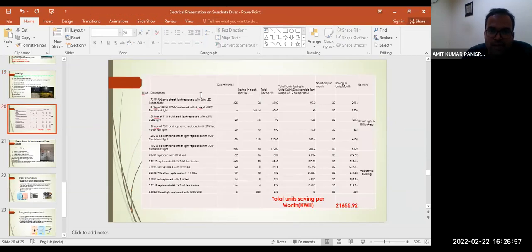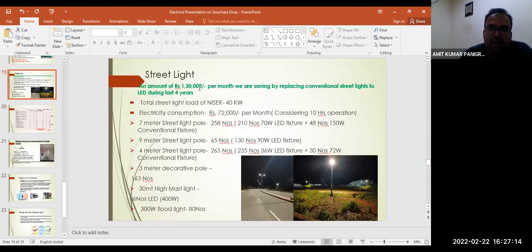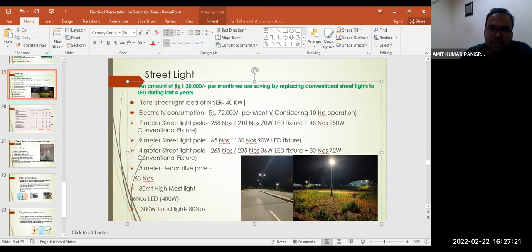If you go into detail, these are the data: previously which type of fixtures they were using, and now which type of fixture we have changed to. In total, we are saving around 21,600 units per month. If you monetize it, it comes to 1,30,000 per month. It is only in 4 years that we have changed this. Now around 80% of the street lights are LED and 20% are conventional, which we will gradually change. The load is 40 kilowatt, and we are spending around 72,000 per month on street light, considering 10 hours of operation.